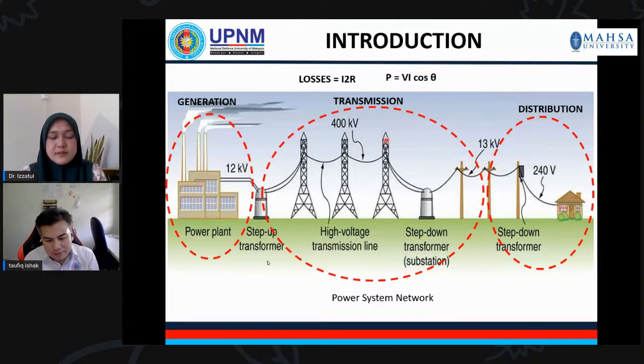So to avoid having higher losses, we can calculate the losses using the formula. The most popular formula for electrical engineers is I squared R. Current squared multiplied by the resistance of the cable, any cable. So the higher the current, the higher the losses. And then how to reduce the losses? We can control the amount of current that flows through the transmission line. The resistance of the transmission line is fixed because the distance of the transmission cable is fixed. Normally the resistance of the cable is also fixed. So the only variable that you can control to reduce the losses is the current.